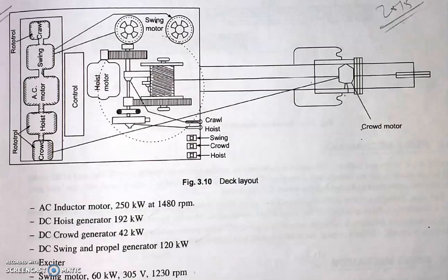The figure shows the deck layout of the electrical shovel. The principal power equipment is the motor generator set. The MG set is usually placed at the rear side of the machine and consists of an AC induction motor, swing generator, hoist generator, crowd generator, and exciter.